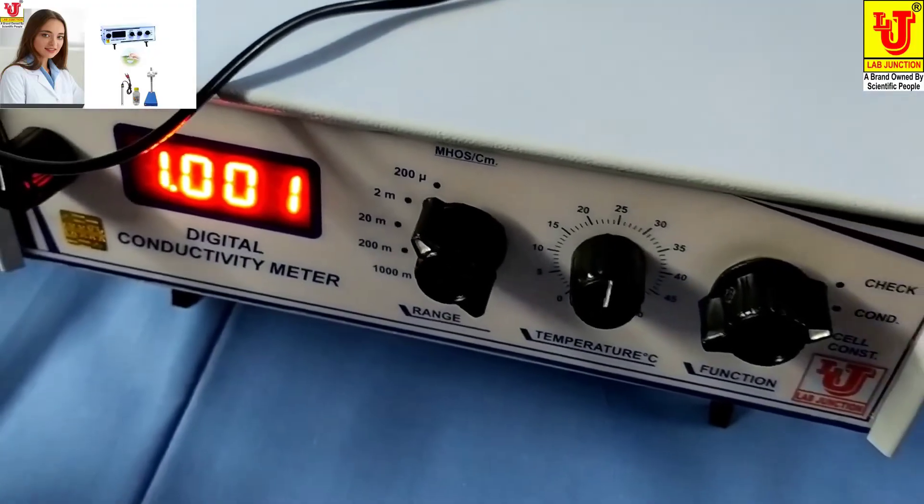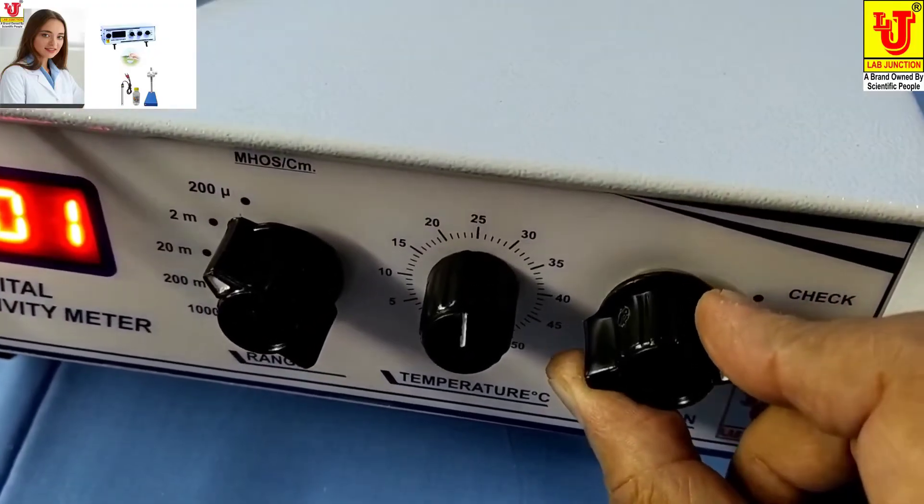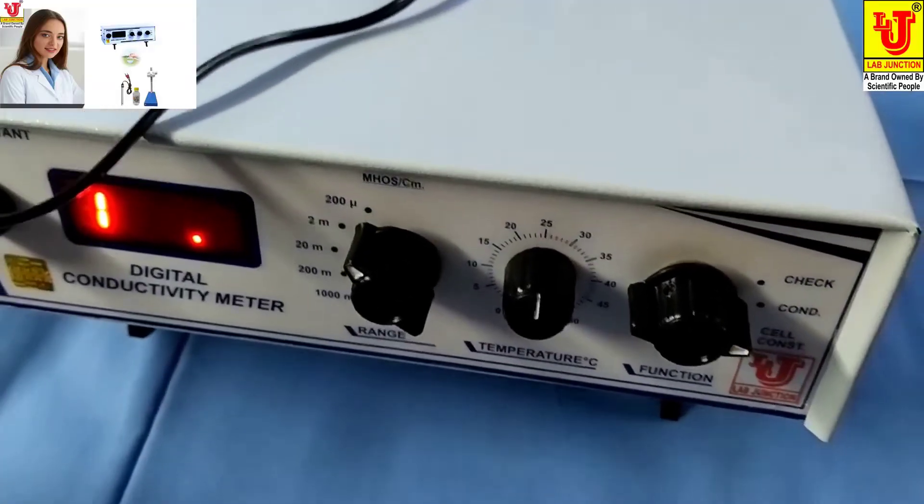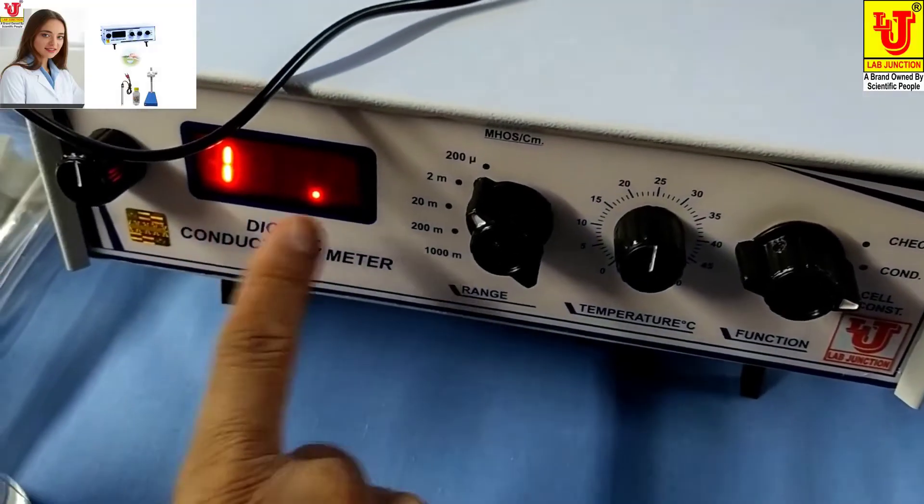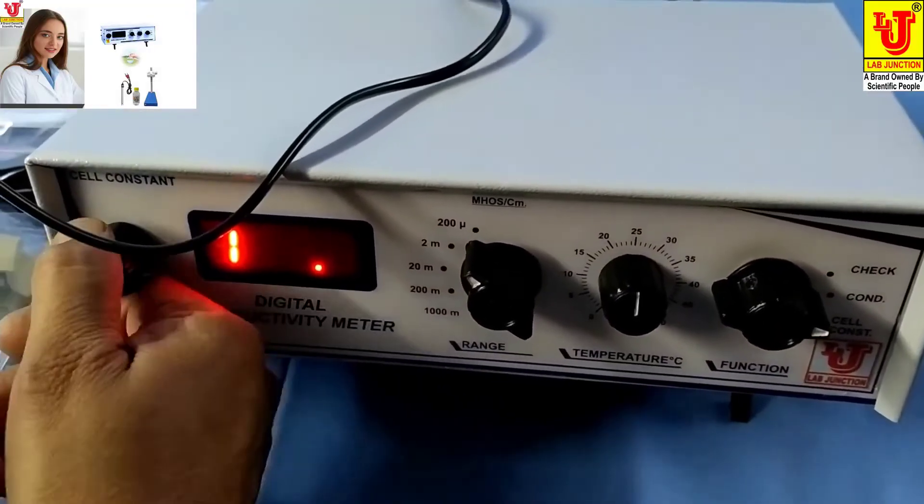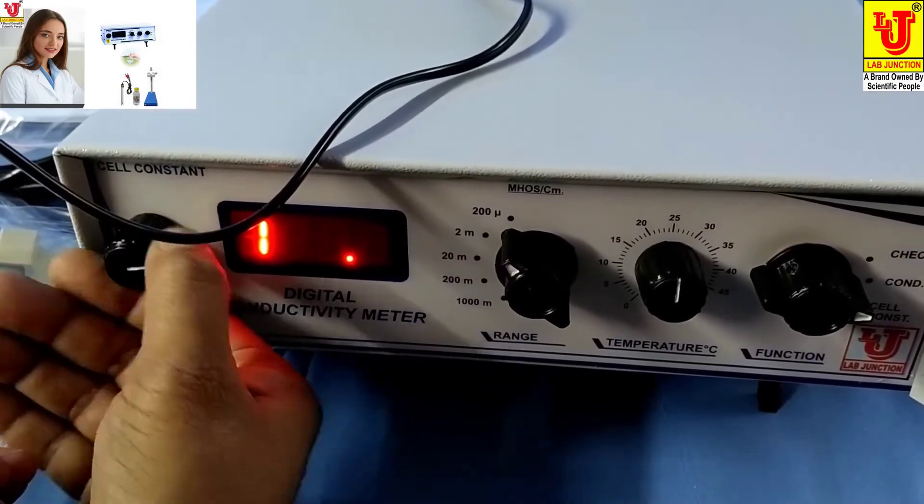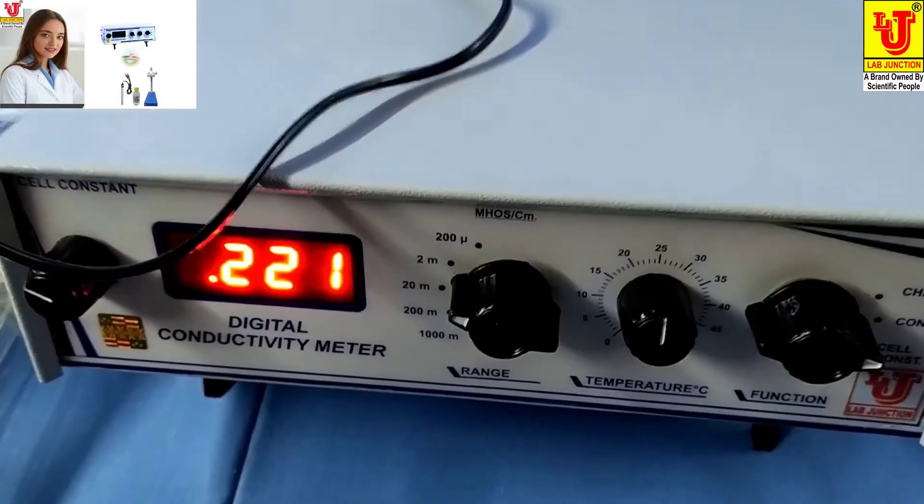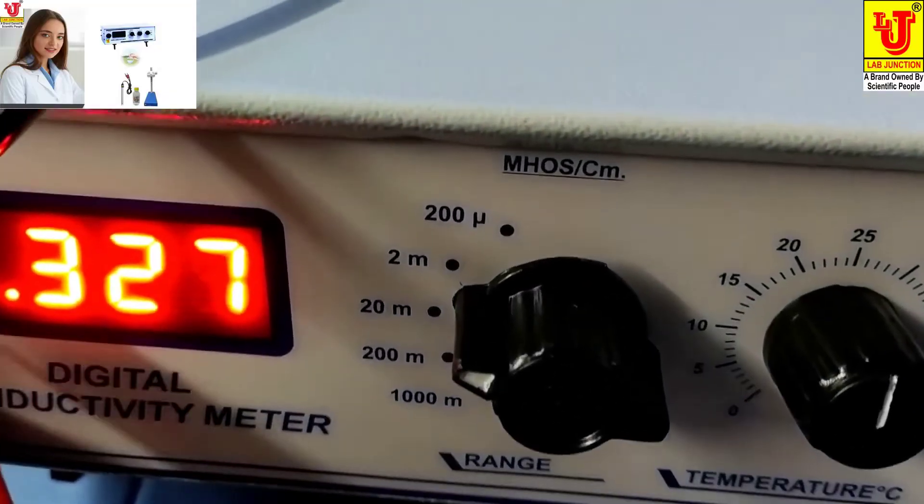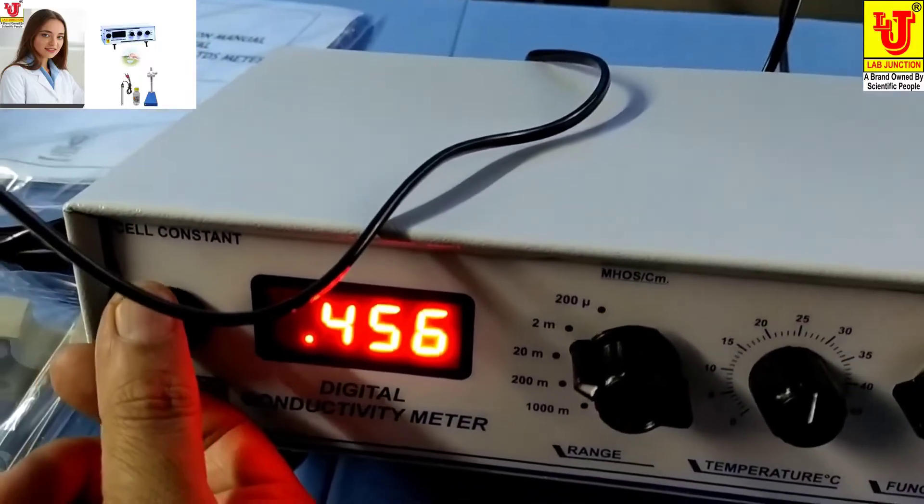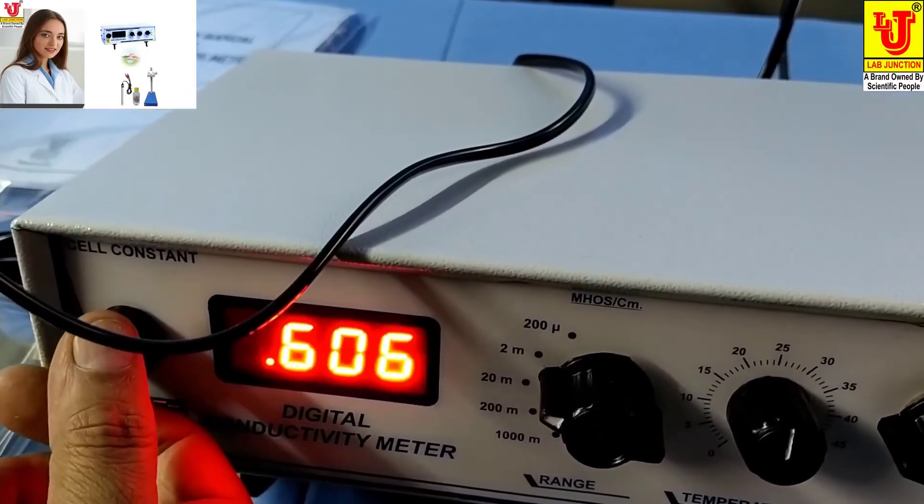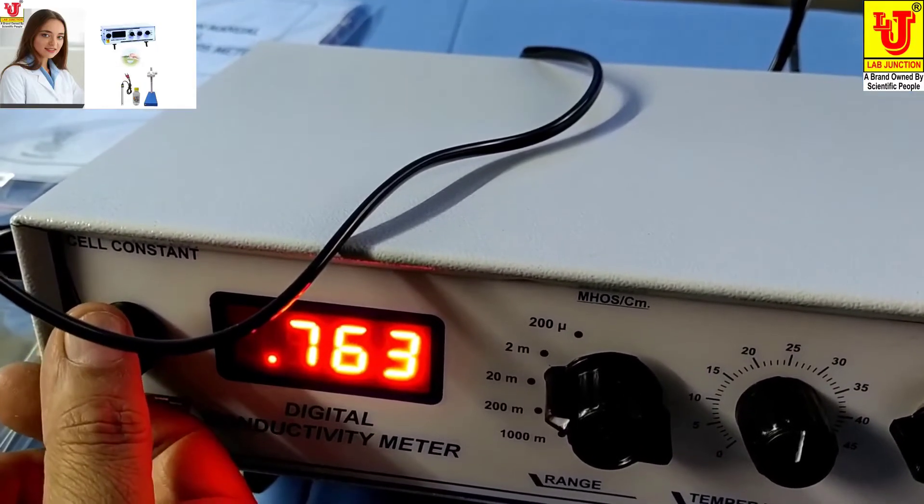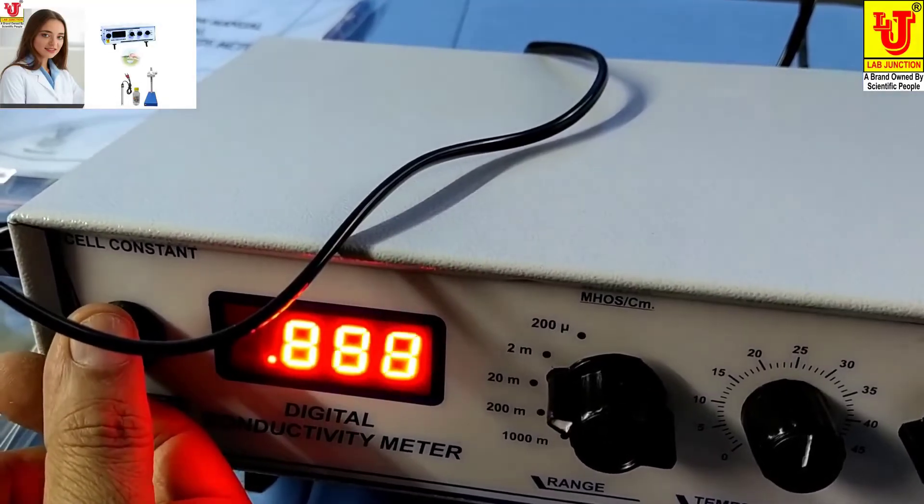Now first, you can set to conductivity position. Now this is our range on first position, like we checked again. Now you can do on second range and set it to your known standard solution value, 1 millisiemens.